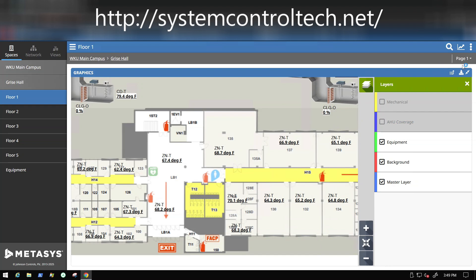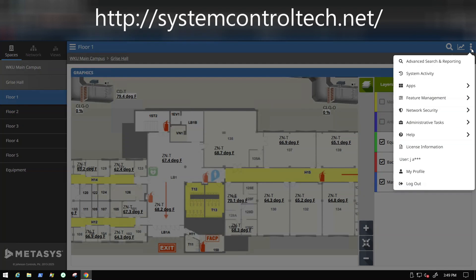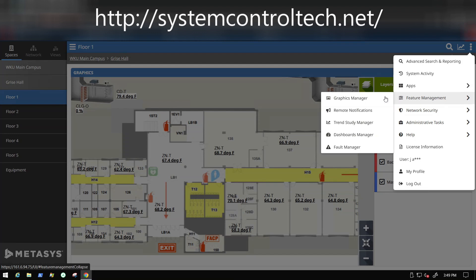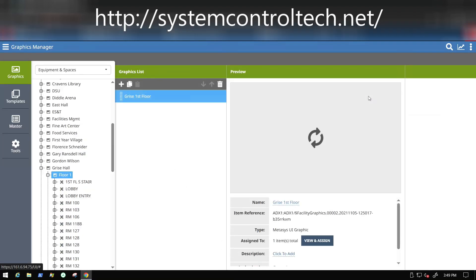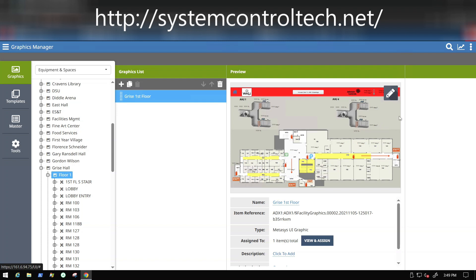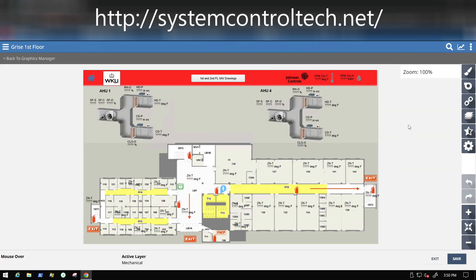Changing these and setting these up is quite easy, and the way that you do it is within your graphics editor. I'm going to go to the skinny snowman icon in the upper right-hand corner, select Feature Management, and then go to Graphics Manager. This is going to bring me into the graphics manager where I can edit or change whatever I need to for this particular space. Since I was in the first floor space, it automatically took me there. When I hit the Edit button, it brings me into the space. To add or change things related to layers, I want to select that stack of books — the layers icon. When I click that, it brings up the edit panel where I can turn layers on and off.